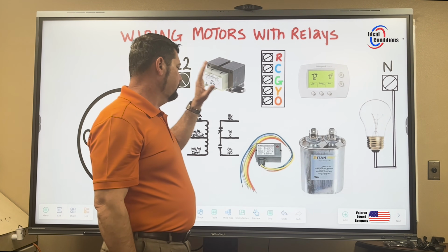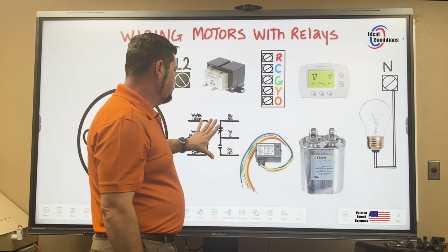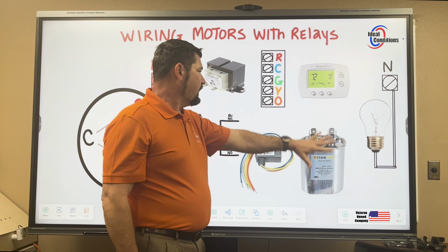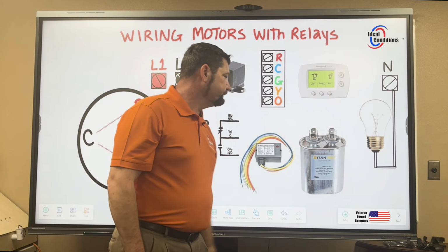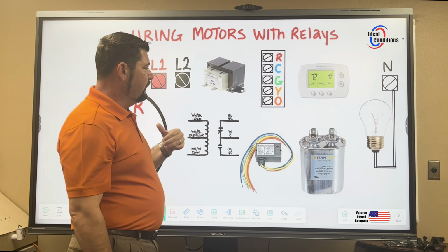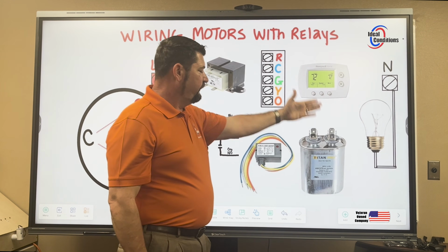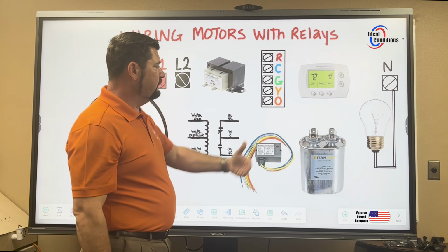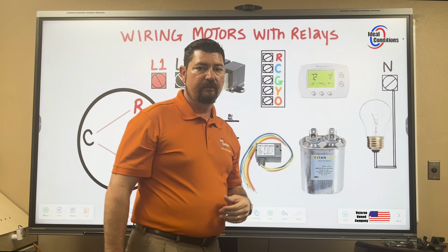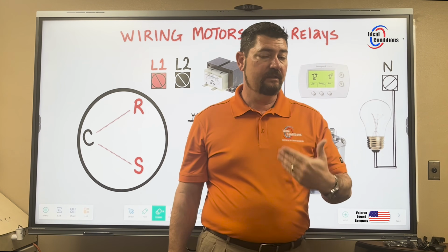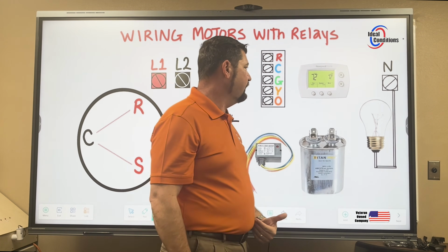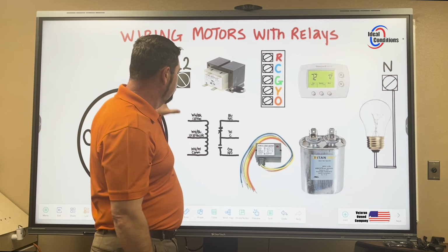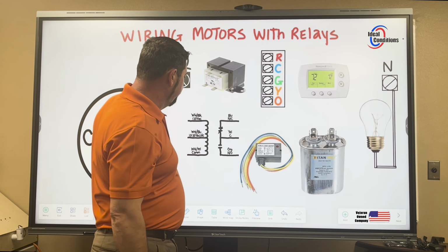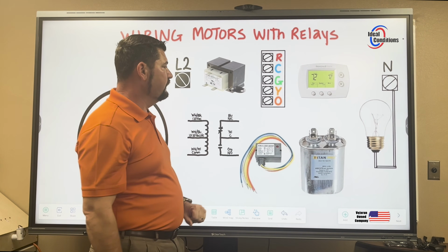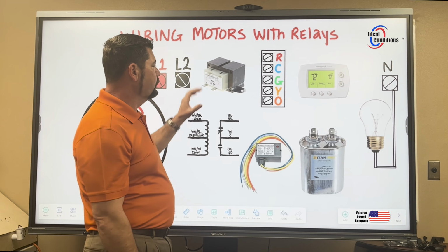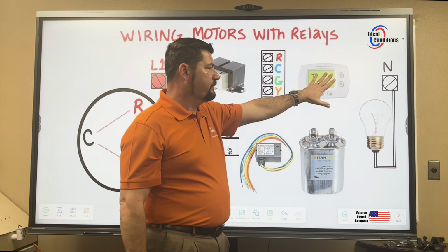The purpose of this video is to make sure that you understand how to wire these contacts and these coils based on what I have up here for L1, L2 and neutral with these loads. All of this stuff is still going to be relevant. However, like I say in a lot of these videos, we'd have to sit here for 90,000 hours to talk about everything. But as of right now, we're just trying to figure out how we take L2 and L1 and wire this motor up with this relay, but also because we're using coil voltage, we need 24 volts. And yes, the thermostat has to toggle that.